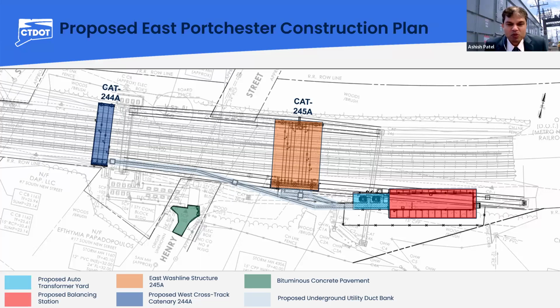The installation of the proposed balancing substation building requires an elevated substation foundation to keep any kind of water from coming inside the cable vault. The new walk-in type vault will be constructed for placing the new balancing substation enclosure and pulling cable in and out. The new balancing substation will be constructed as a prefabricated walk-in type metal enclosed building. It will house various traction power equipment. The blue color block represents the proposed location of the auto transformer. The new auto transformer yard will be designed on the west side of the balancing substation. The new 8 feet high chain link fence will be designed to deter anyone from coming into the auto transformer yard. A total of 2 new catenary structures will be constructed to support the disconnect switches and a new aerial wire on the New Haven main line.